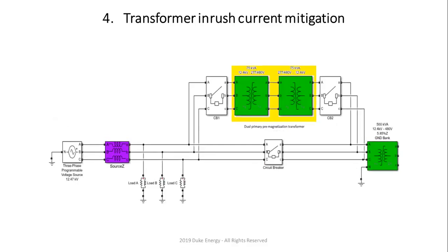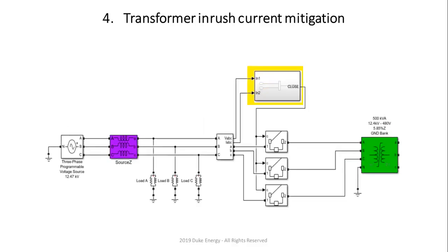We actually put 2 transformers back to back. Normally you close circuit breaker 1, which energizes these 2 transformers, then you close circuit breaker 2, and that energizes the big transformer through the 75 kVA transformer. Once that is energized, you close the main circuit breaker, and then you trip circuit breakers 1 and 2. Unfortunately, the smallest transformer that I could find that is built is 75 kVA. So we go from 1247 to 277, 480, and then we just flip-flop. 75 kVA is the limiting factor, so that means the current would have to be higher. Plus, if you ever install this, there's significant cost because all of this is high voltage equipment.